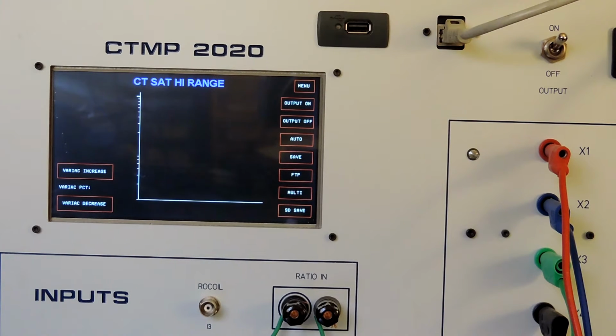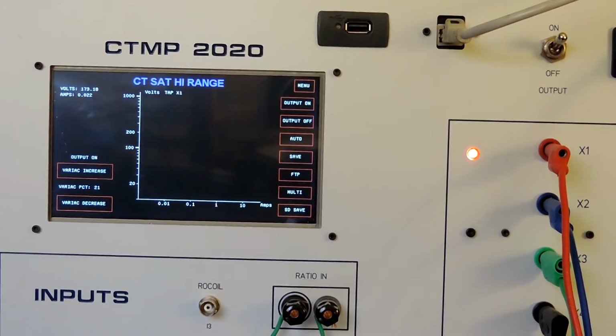It has now completed all the ratio tests. I'm going to do the saturation tap test on X1 through X4. The red light is lit because the red jack and the red wire is energized. And it's doing this without any intervention from me. I'm not doing anything.